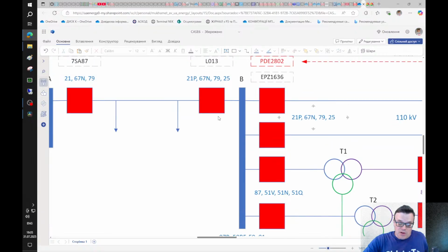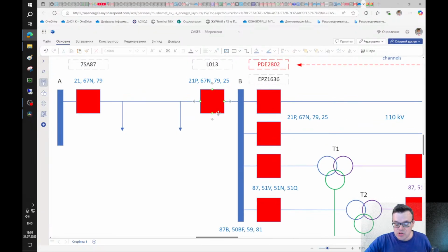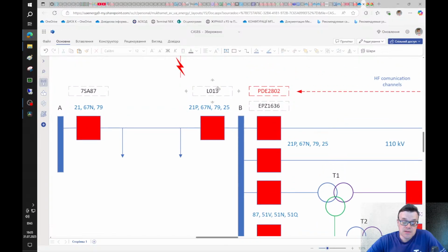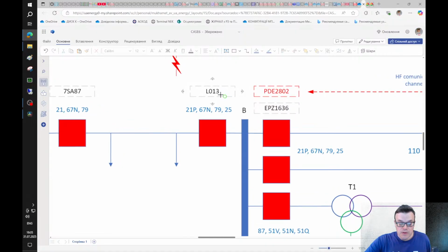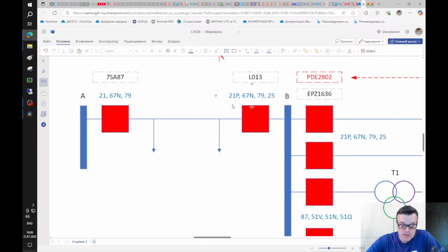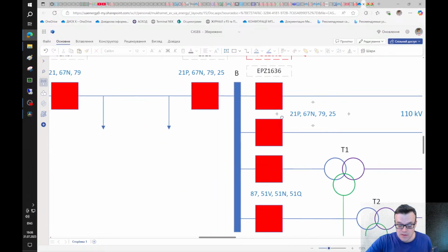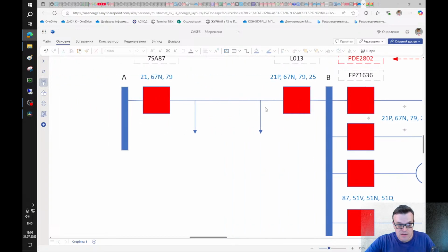Because I don't want to put any sensitive information, the primary scheme of the power plant is a little bit weird, but it can be said that it has one bus with a transfer bus. So this line was worked through the transfer bus circuit breaker, and this circuit breaker has its own protections made with a Ukrainian microprocessor-based relay that has the same functions as I described.